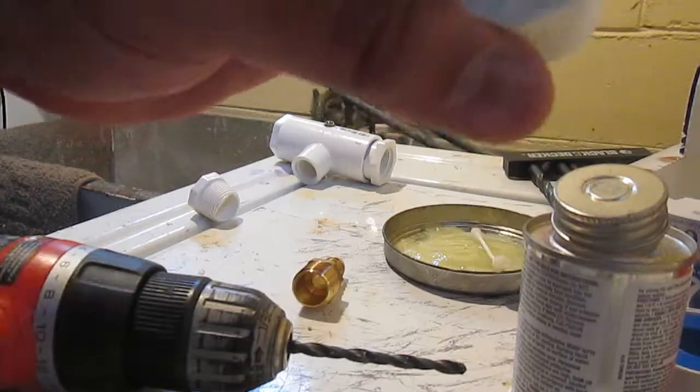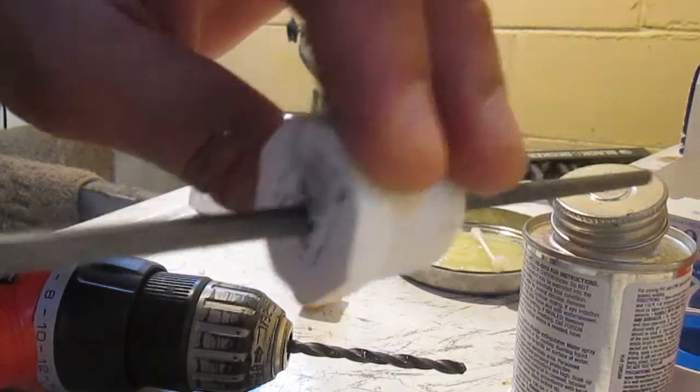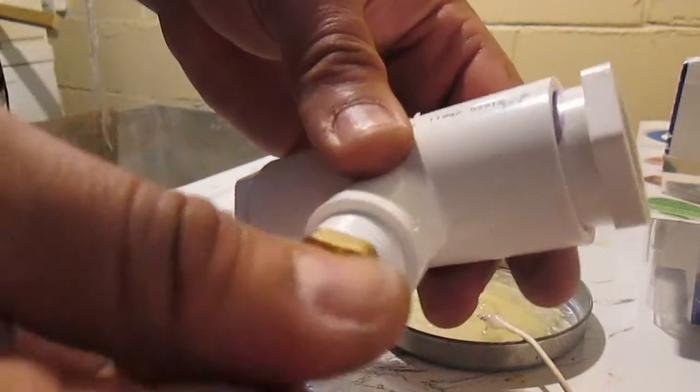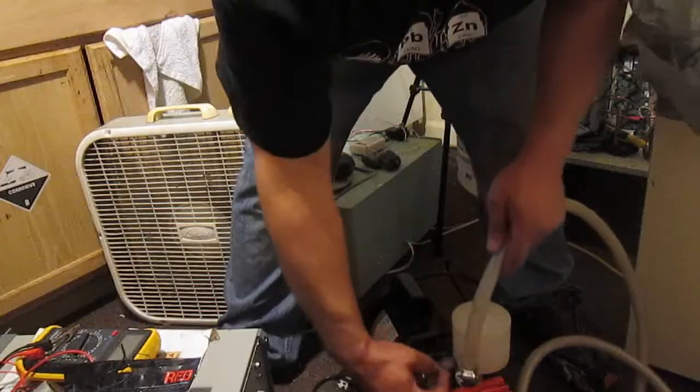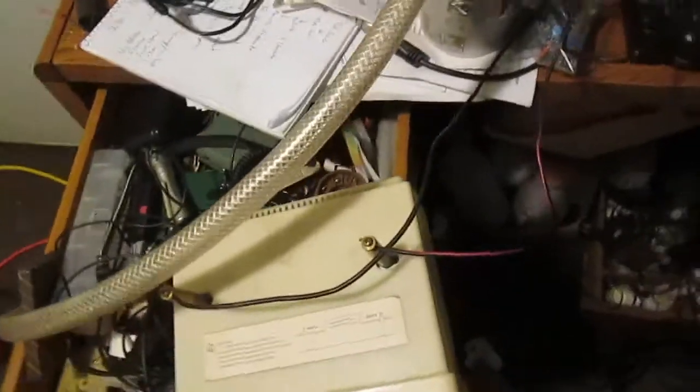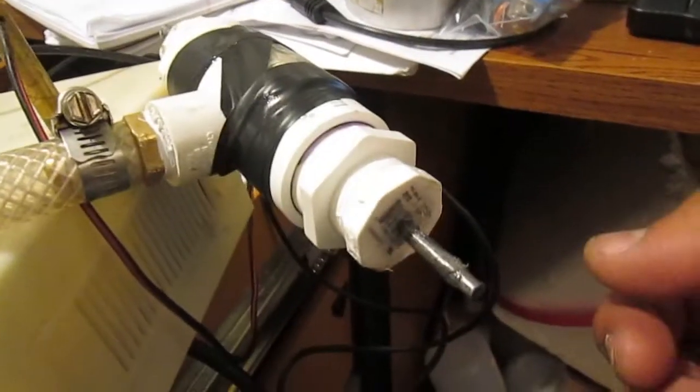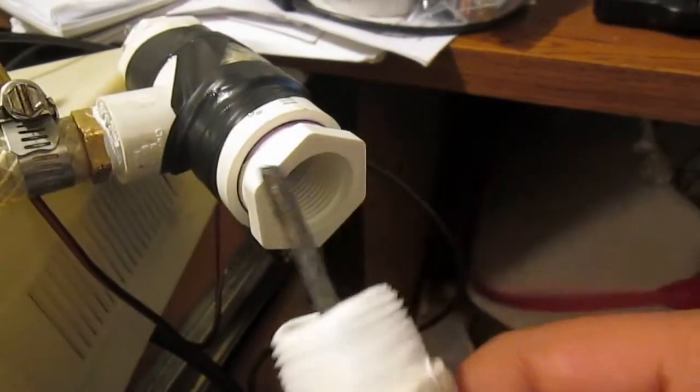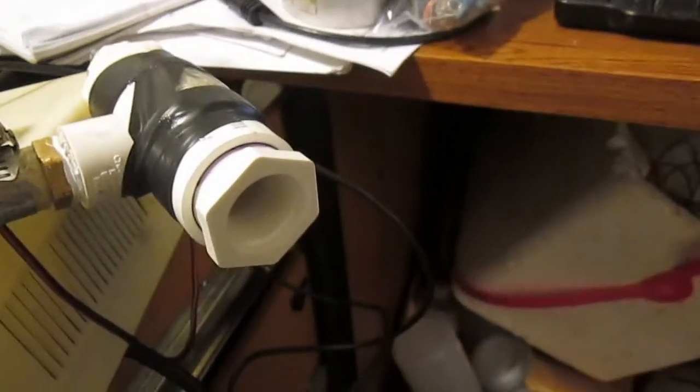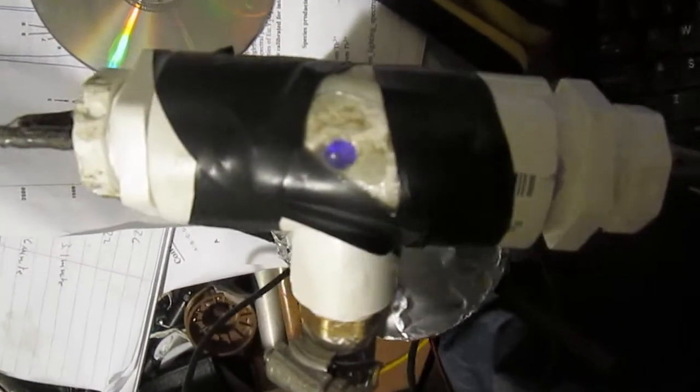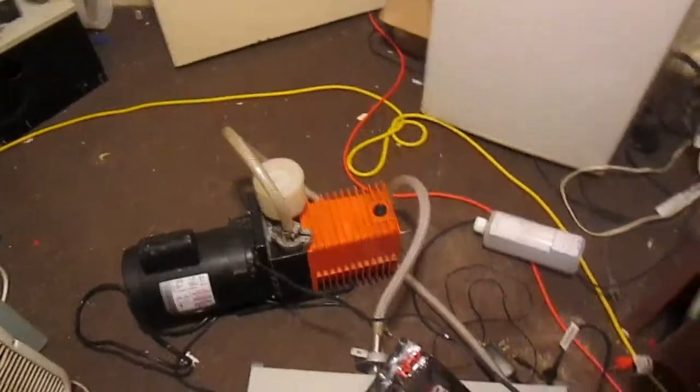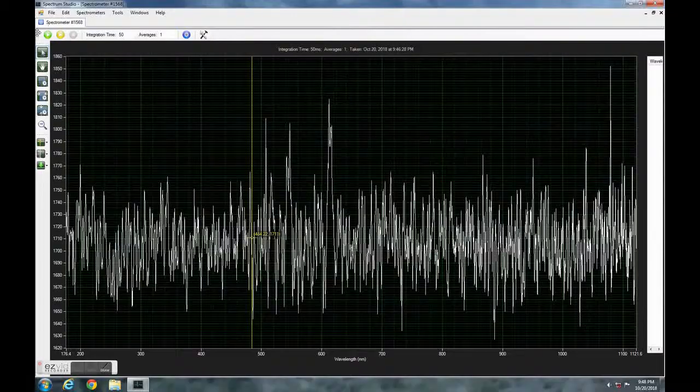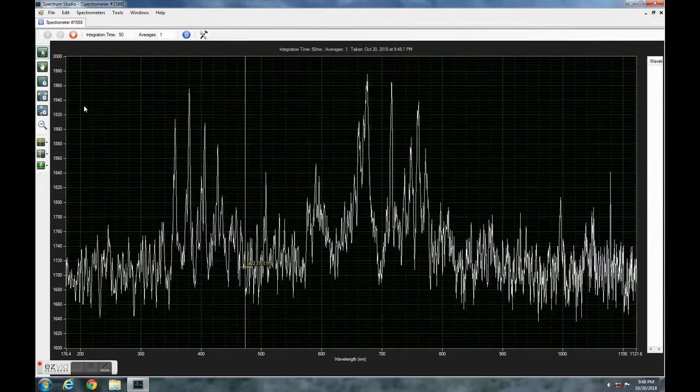So basically the atoms left in the chamber, mostly oxygen and nitrogen, are being ionized by the high voltage. The ionization process involves an atom losing or gaining electrons. These electrons change shells either up or down. When moving up they absorb energy, when they're moving down closer to the nucleus they release some energy. Now the amount of energy involved is a few electron volts, so only the outer shells are being involved in those processes. The energy released in the form of photons is specific to those atoms, so we can determine what type of atoms are present.